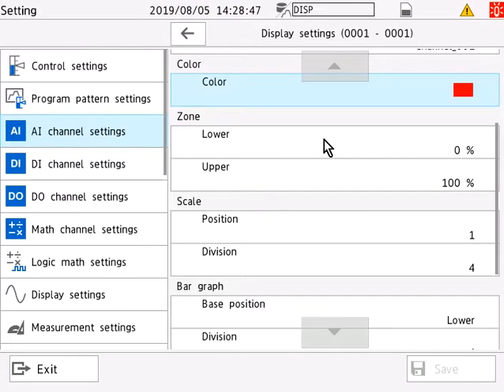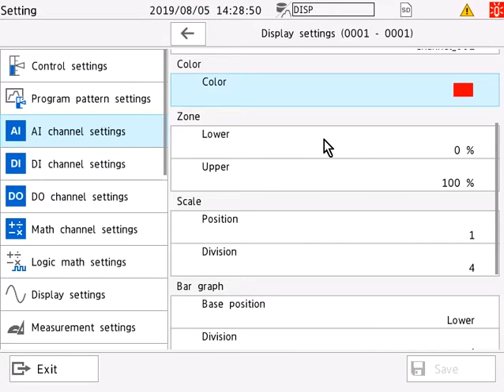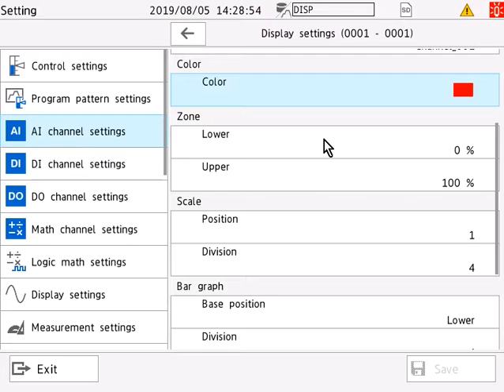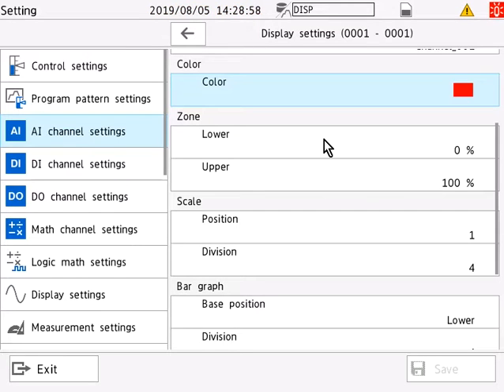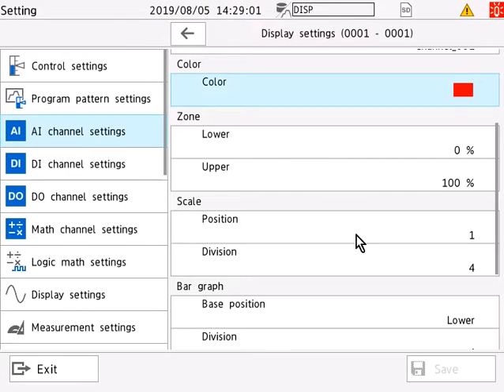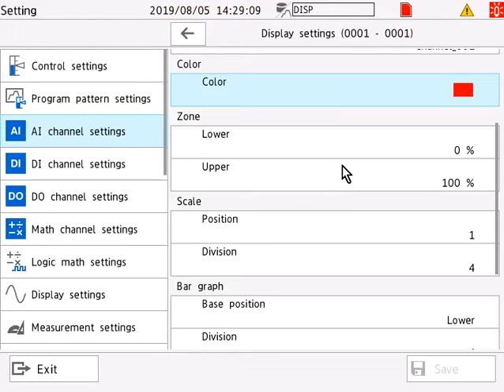Moving on to the zone settings, here you can set these values when you want to divide the waveform trend displays, such as the one we've just seen in the trend display, into separate zones so that the trend displays do not overlap. Set the lower and upper percentages to a percentage less than the upper and set the zone width to be 5% or greater.